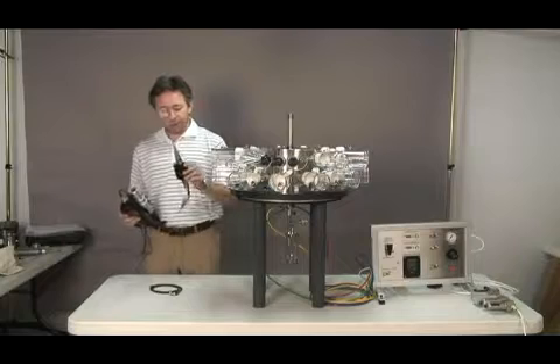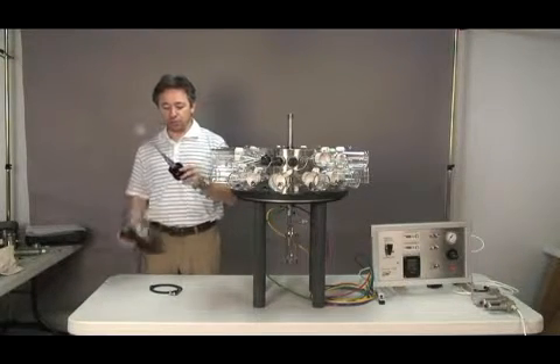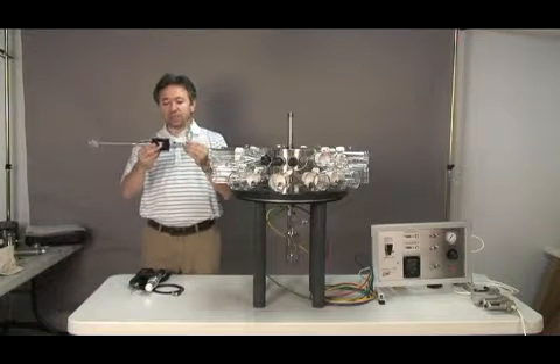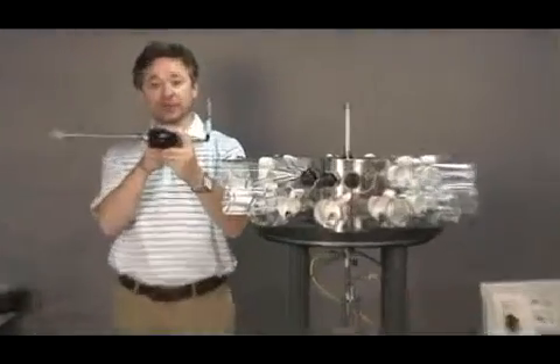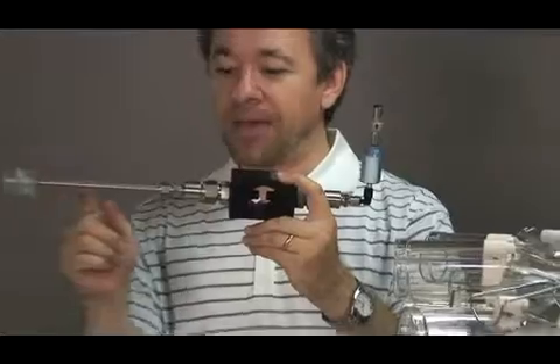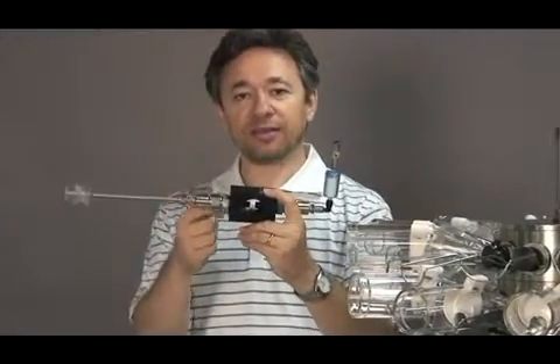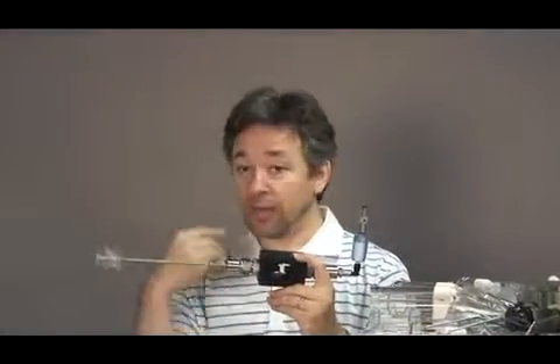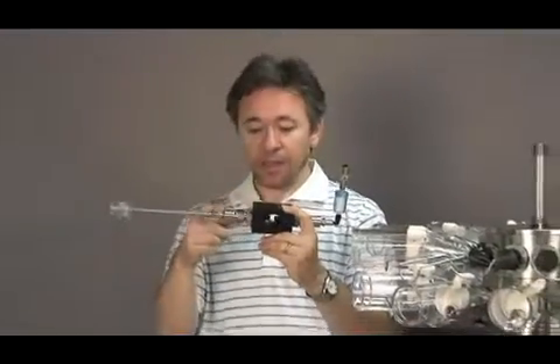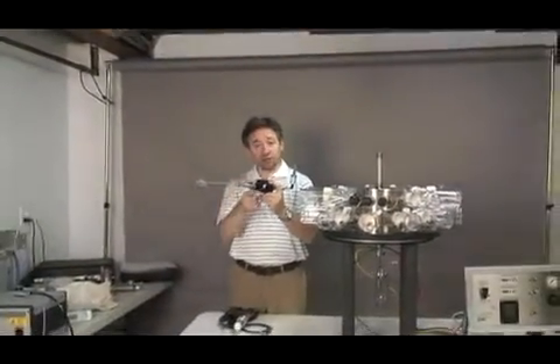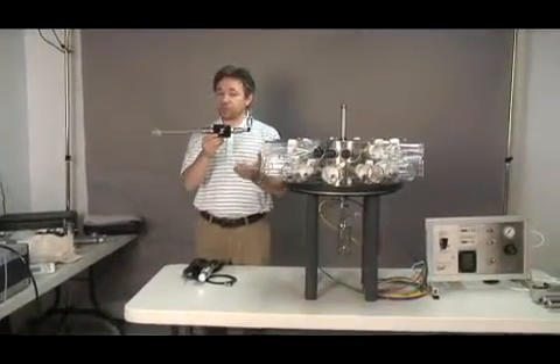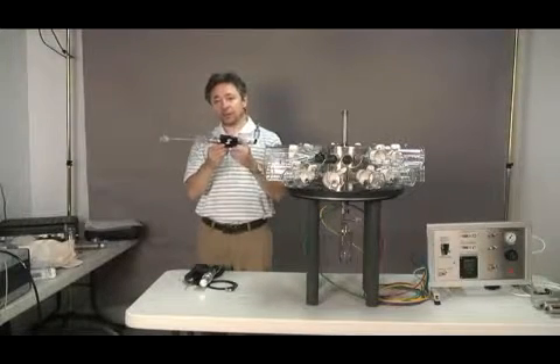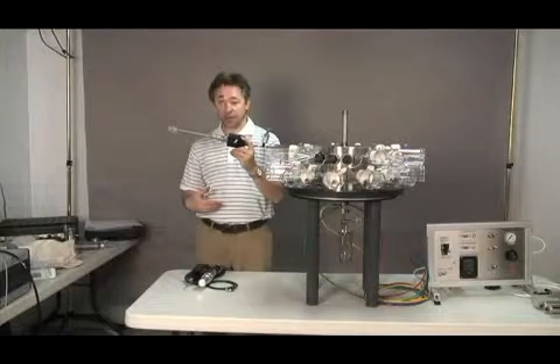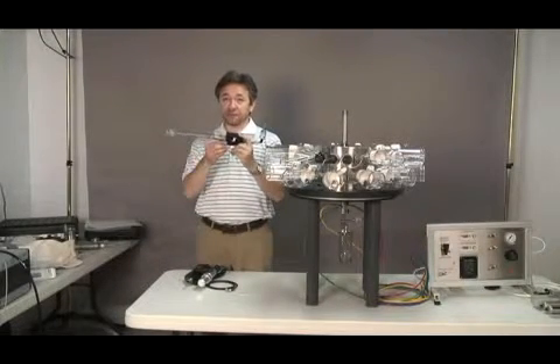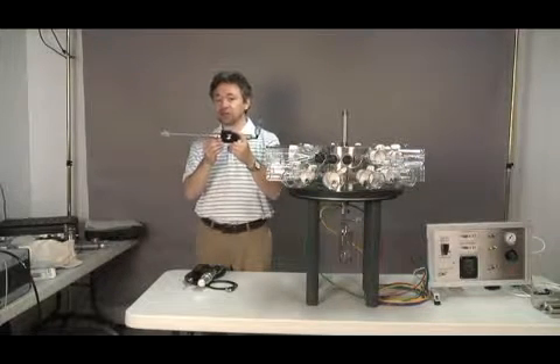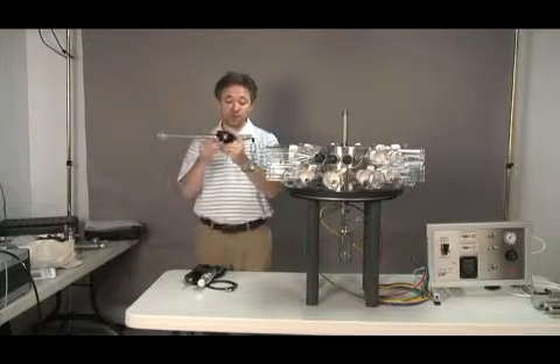The monitor is equipped with a special device which is called a clear lens adapter. It is a specially designed cuvette that makes sure that the aerosol flowing through it is flowing in a laminar mode, which means avoiding turbulence and avoiding the aerosol from basically being lost inside the probe. So we have two benefits. First of all, we have a more accurate measure of the aerosol. Second, it extends the life of the probe in terms of cleanliness, which means that we don't have to clean the lens so often, because the probe has to be sent to the factory in case it's dirty.